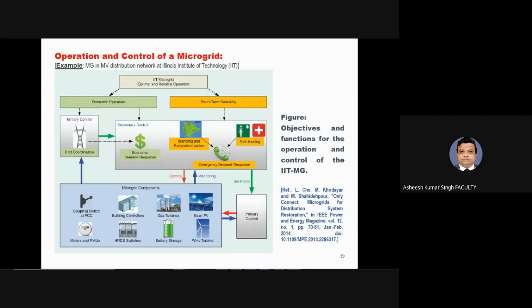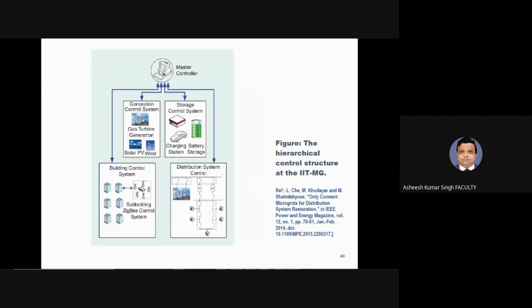So this primary control is performed at the DER level. Here you can see the primary control is used over here in the distribution resources, so at this level it is done. The master controller performs the centralized secondary and tertiary controls, and in this way it moves on. These are the building control systems, and this is the distribution control system, which goes again directly to the master controller, controlling in both directions.